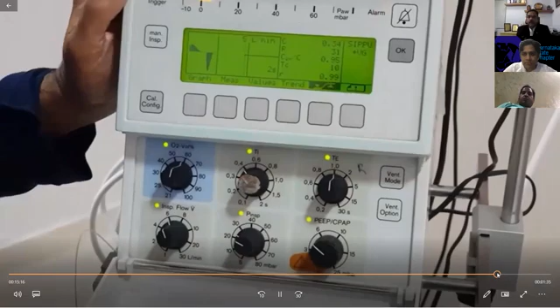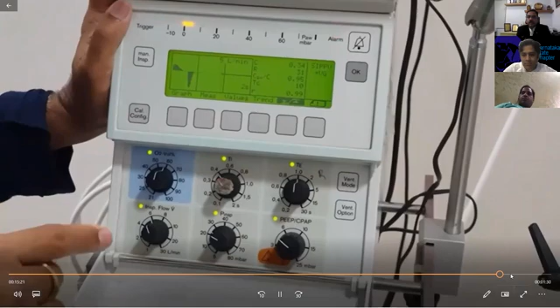you have the ventilator set on SIPPV with volume guarantee. The similar method can be employed to use the volume variation, but at the end of the day, they always deliver whatever is the volume guarantee. It's only the technique which is different, but ultimately both of them effectively deliver the volume. So this is about the practical demonstration for the conventional ventilation with patient triggering and volume ventilation in either of these ventilators.